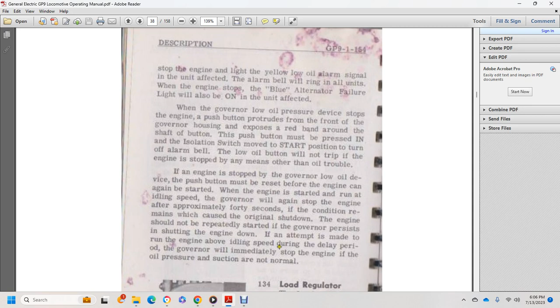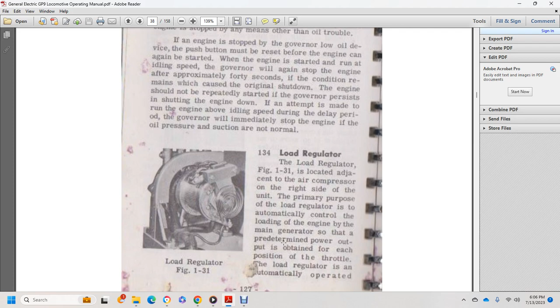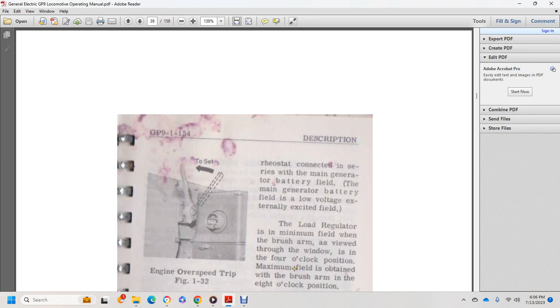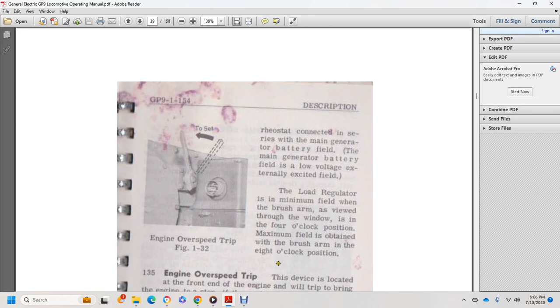Alright, 134, load regulator, figure 1-31, located adjacent to the air compressor on the right side of the unit. The primary purpose of the load regulator is to automatically control the loading of the main generator so that the predetermined power output is obtained. The load regulator is automatically operated. The rheostat is connected with the battery field of the main generator, a low voltage externally excited field. Minimum field is obtained with the brush arm in the 4 o'clock position as viewed through the window. Maximum field is obtained with the brush arm in the 8 o'clock position.